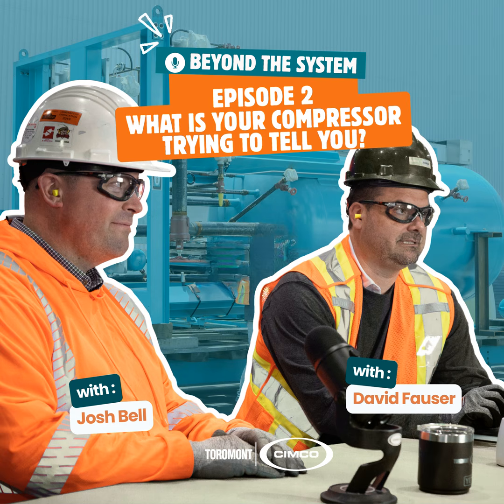Say it's time to schedule an overhaul based on hours, and they open the machine and there's a critical component that's worn. Just because it hasn't broken yet doesn't mean it's not worn. We're doing maintenance within tolerances, and we're measuring. For example, if you needed a crankshaft in an emergency, you're probably not going to find one, so you'd likely replace the compressor instead, because they're not always available. But if you take it down in April and don't need to start until October, I can order a crankshaft and come in 8 weeks later to finish the work.